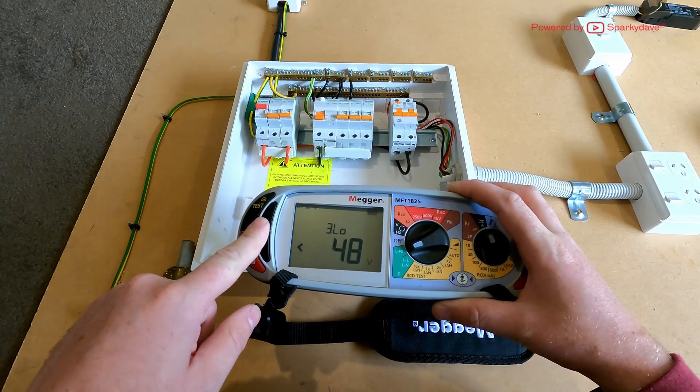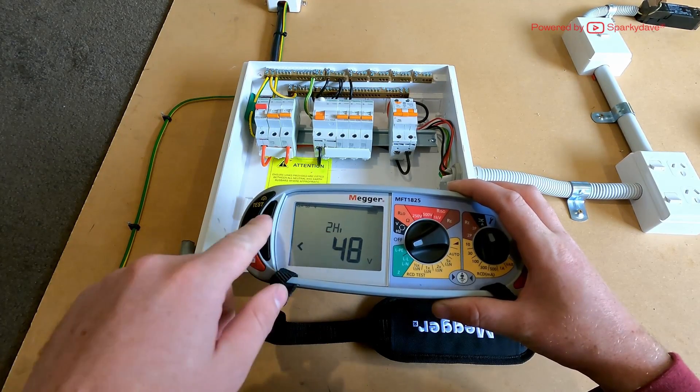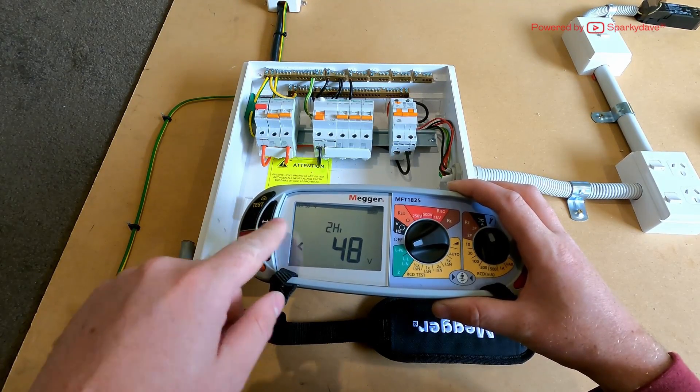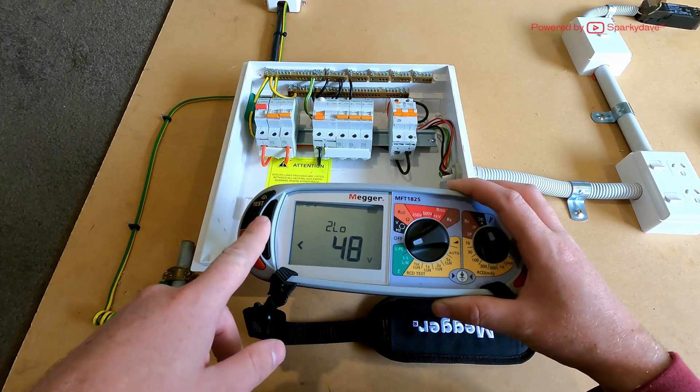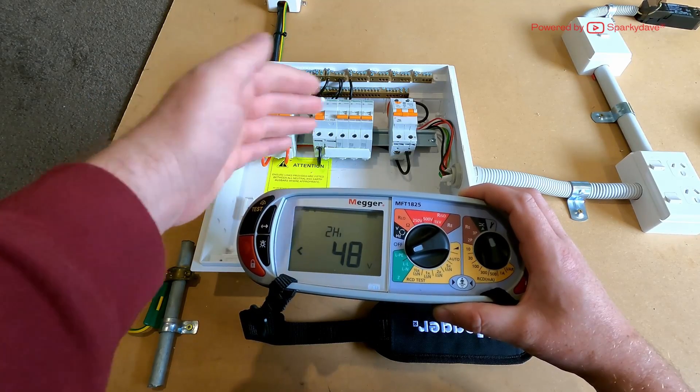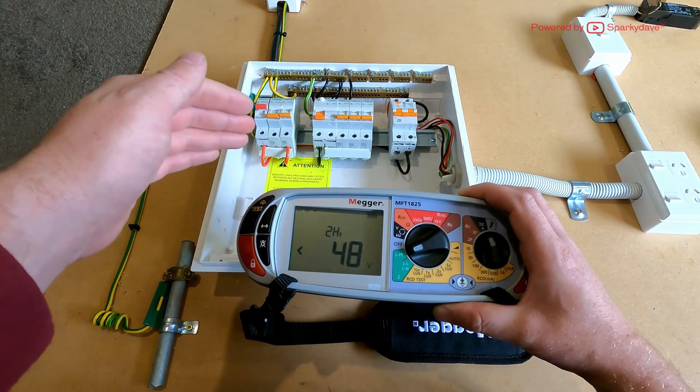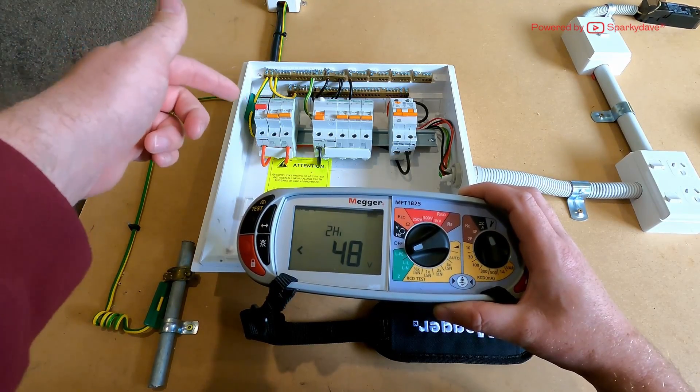If you push the select button here, you can go between the other two lead tests. There's two high and two low. First of all, the two lead high current test you want to do on the line side of your RCDs and the switchboard. We're going to be testing from the line side of the main switch.